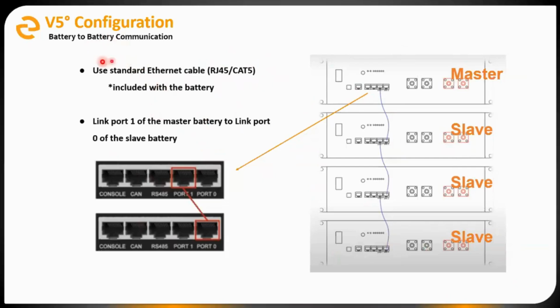So where we're starting here, we're assuming at this point in the process, the installation has nearly been completed. What I mean by that is we've got batteries mounted or in a cabinet, our inverters mounted, everything's connected, all of our power cables are run, everything's in conduit. Basically everything is ready to go and to be turned on for the first time. Before we hit that on button for the first time, and again, all of our power cables and mechanical stuff has been completed.